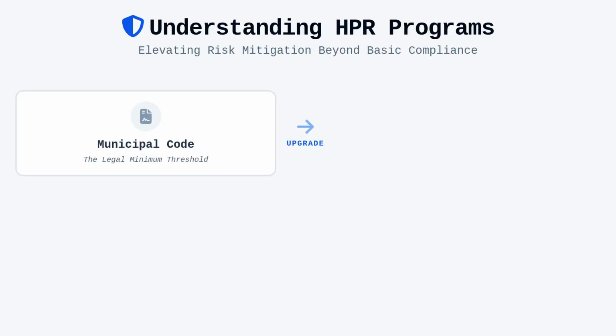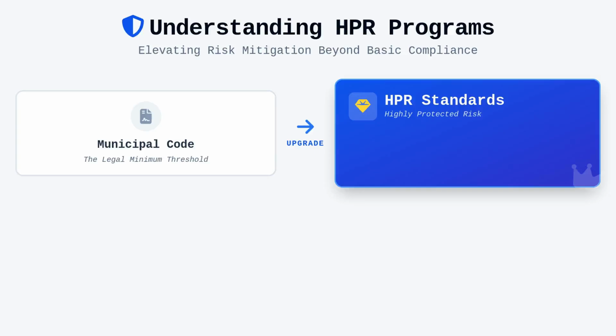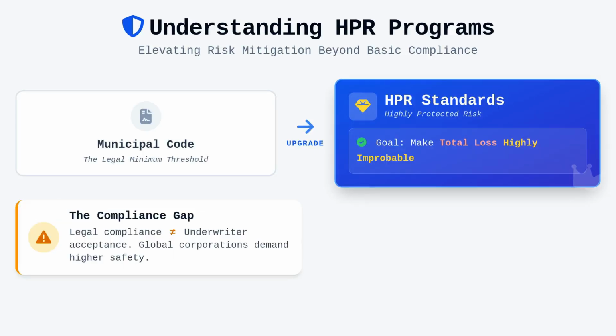In the professional landscape, we occasionally encounter the assumption that meeting the minimum requirements of a municipal building code is sufficient for business operations. While code compliance is legally mandatory, it often represents the minimum threshold of safety, which may not align with the risk appetite of an insurance underwriter or a global corporation. Highly protected risk, or HPR programs, represent a class of insurance underwriting that necessitates engineering standards significantly more stringent than those mandated by local jurisdictions.